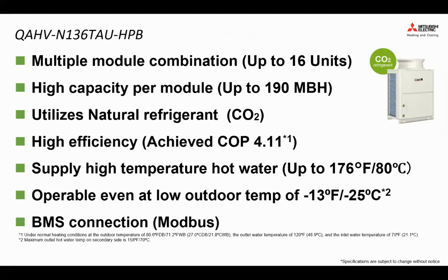So, some additional features, just a general overview. We can have multiple module combinations, so you can have up to 16 units. Each unit has a nominal capacity of 136 MBH. So up to 16, 136 multiplied by 16, you can have about 2.1 million BTU of total heat. High capacity per module: under the right conditions, in summertime, the unit can operate up to 190 MBH of heating capacity, hot water.